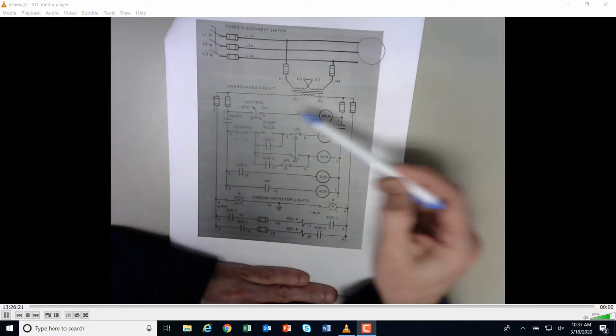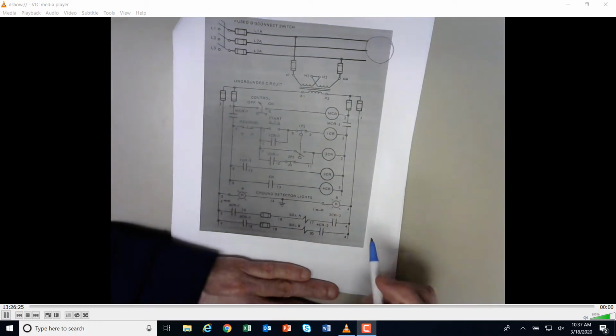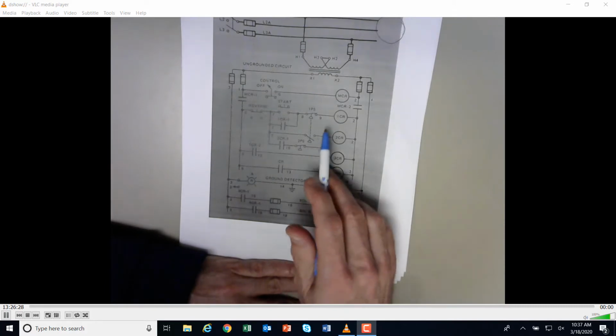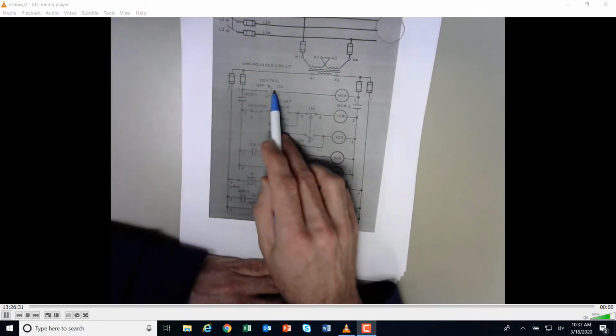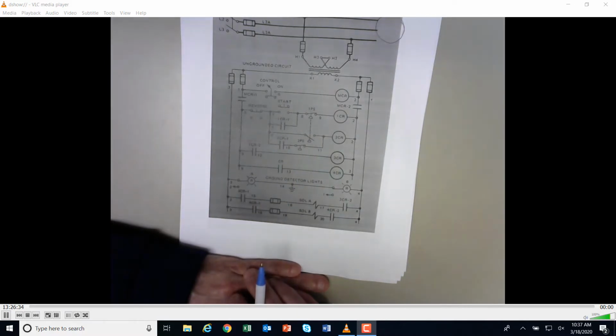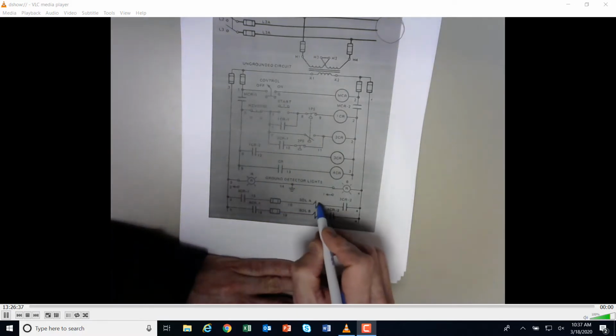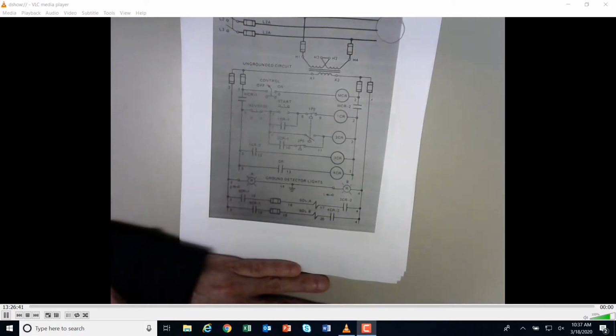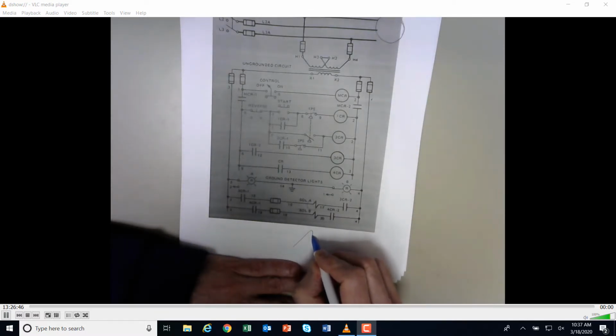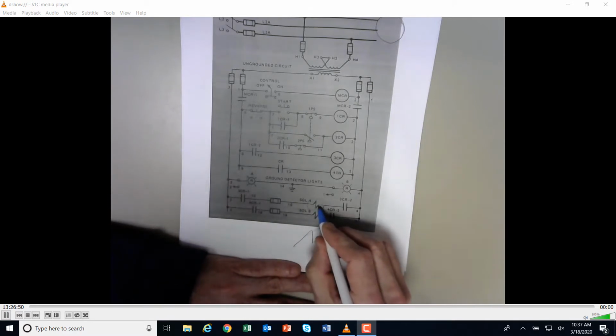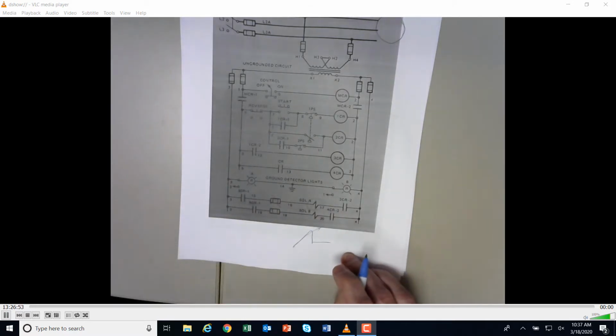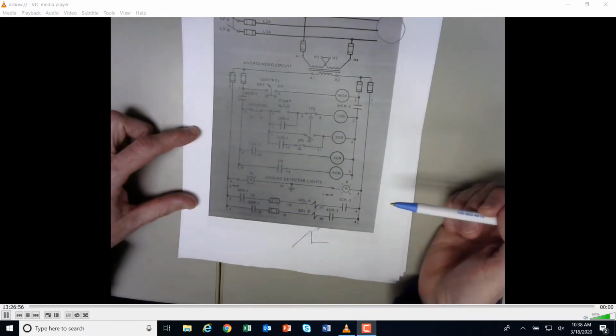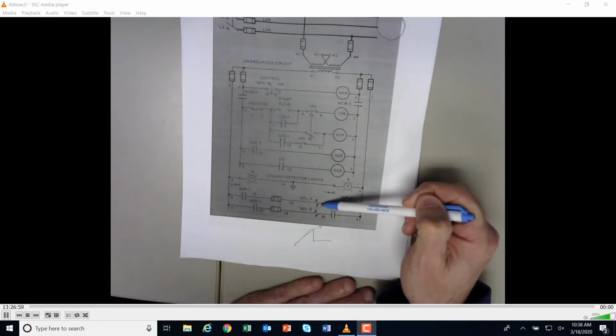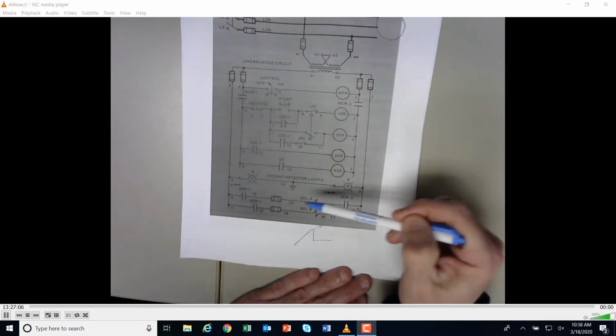What these fuses are doing out here, and what this fuse is doing out here, these are isolating different processes or different items. For example, let's say all my fuses here are good, everything's good, I've got the control relay on, I've got my logic going, the circuit's working, and what happens if for some reason this solenoid sticks and it gets caught into an inrush situation, and that's when the current ramps way up. Instead of coming down to steady state, it just keeps going, and it blows this fuse right there. Well, what's going to happen is everything else is still going to work here, okay? The only issue is that solenoid A is not going to work. So we'll be able to figure out pretty quickly that everything is working here.